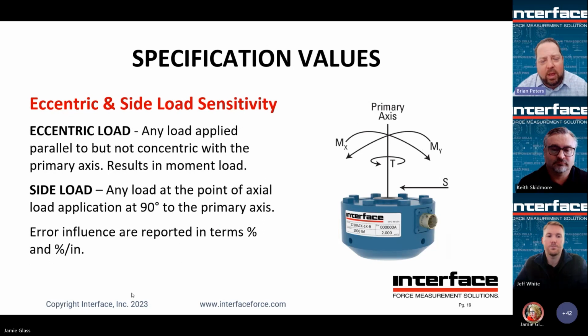Eccentric and side load sensitivity. So you'll find this on many of our products, or actually all of our products that are moment compensated. In particular, our low profile pancake load cells, for those of you familiar with Interface products, the 1000, 1100, 1200, 1600, 1800, 5200. We'll specify how sensitive the sensor is to non-primary axis loading, right? So for an axial load cell, it would be bending moments, it would be a torsional load perhaps, or a side load. So side load perpendicular and eccentric, anything not perfectly concentric with the axis. So these are in percent or percent per inch. So pay close attention to that.